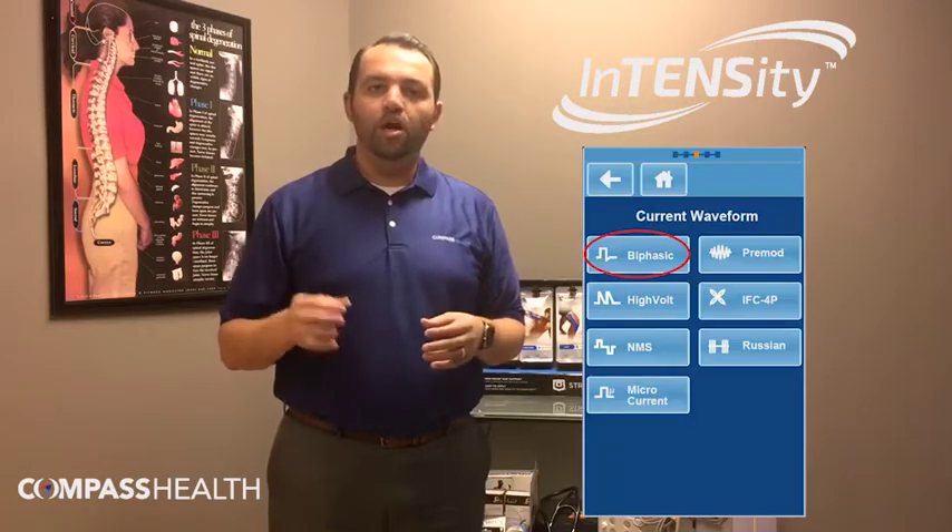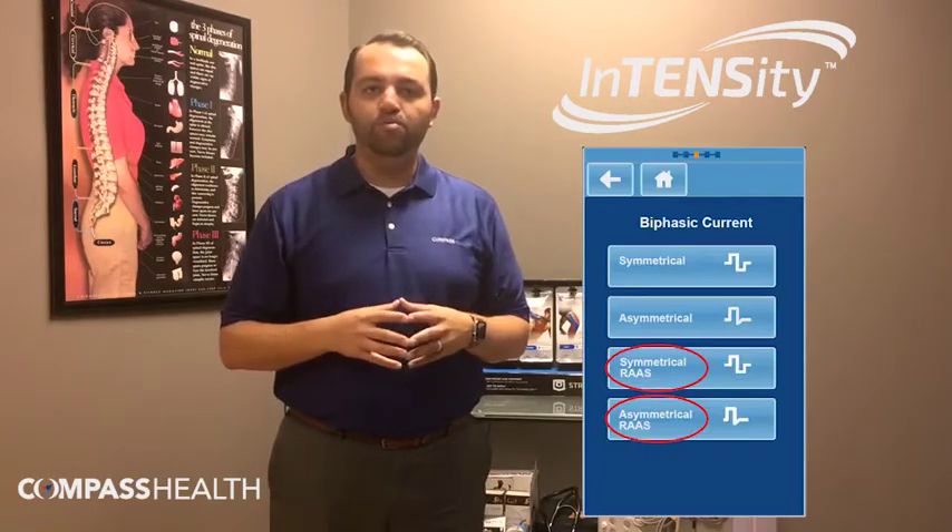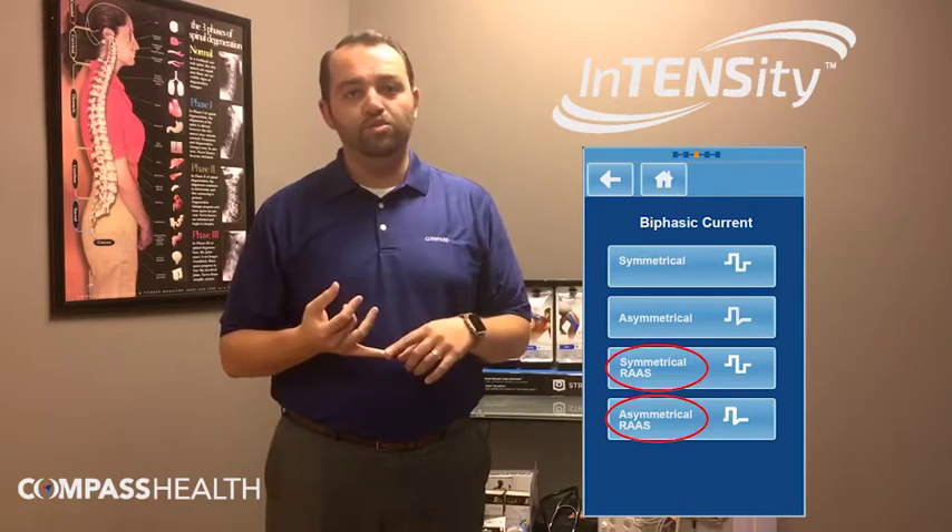All you do is simply go into the electrotherapy section under manual operation and select the biphasic waveform. Once you're in the biphasic waveform, you'll see RAAS asymmetrical and RAAS symmetrical options. Simply select the waveform and you're good to go.